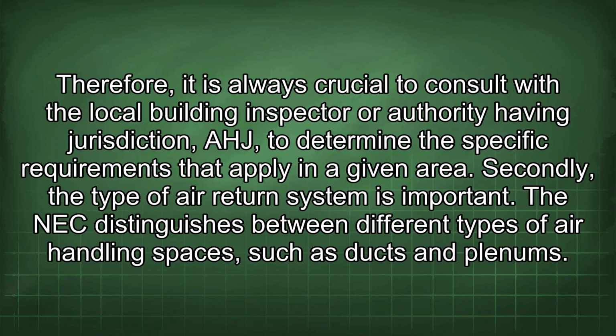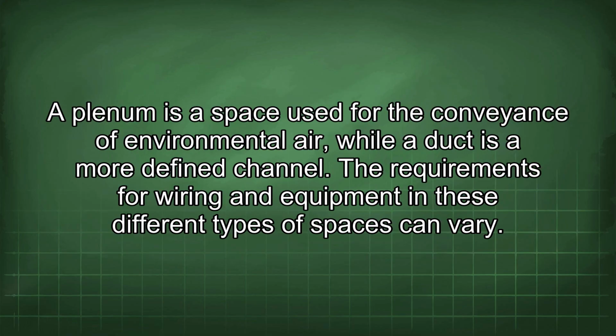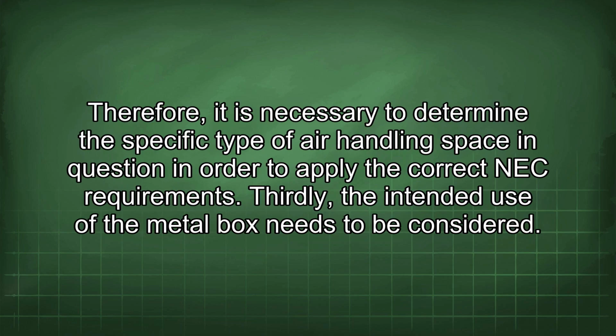Secondly, the type of air return system is important. The NEC distinguishes between different types of air handling spaces, such as ducts and plenums. A plenum is a space used for the conveyance of environmental air, while a duct is a more defined channel. The requirements for wiring and equipment in these different types of spaces can vary. Therefore, it is necessary to determine the specific type of air handling space in question in order to apply the correct NEC requirements. Thirdly, the intended use of the metal box needs to be considered.